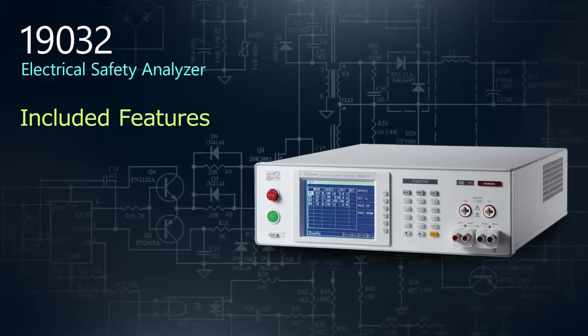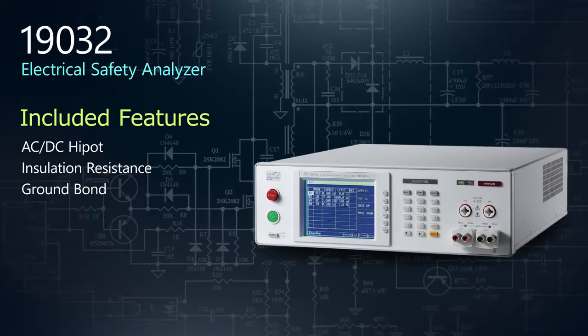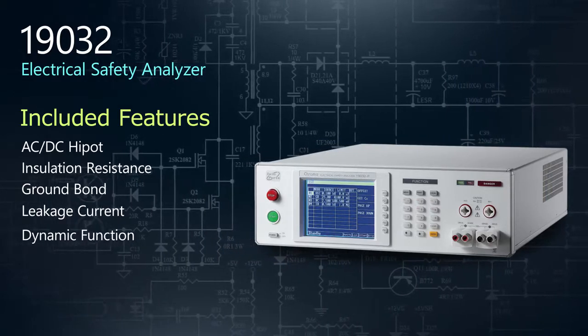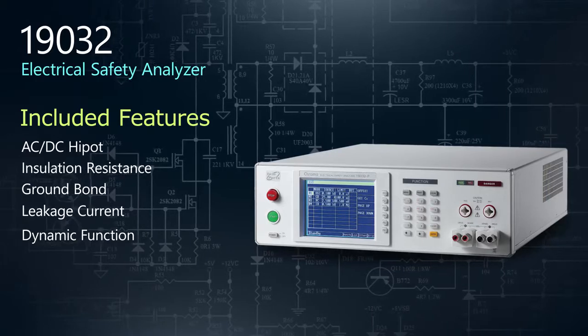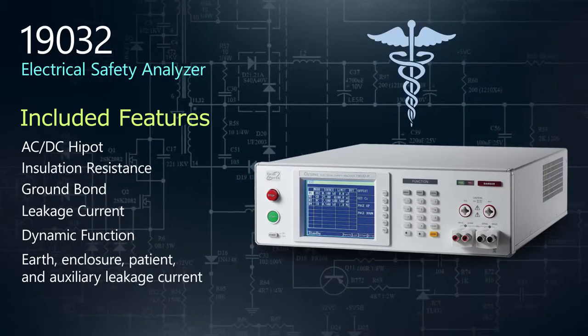Its multifunction design includes AC-DC hipot, insulation resistance, ground bond, leakage current, and dynamic function tests in a compact unit. For medical device testing, scanners are also available for advanced leakage current tests.